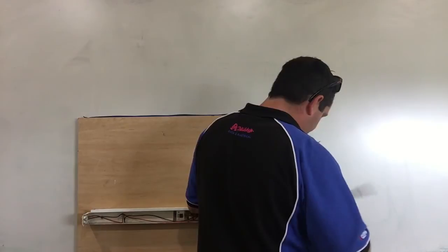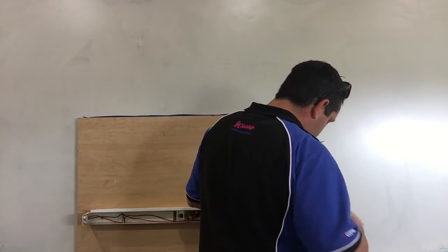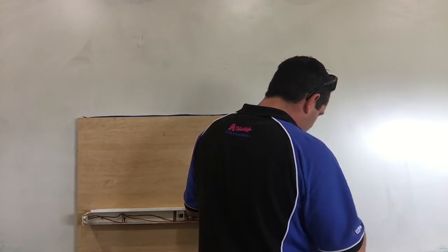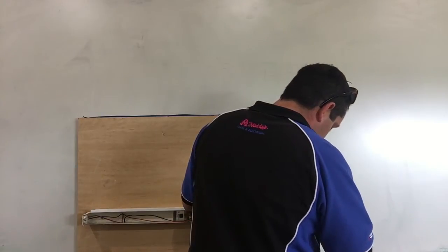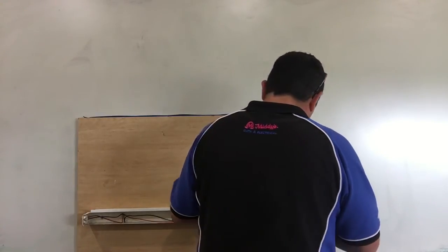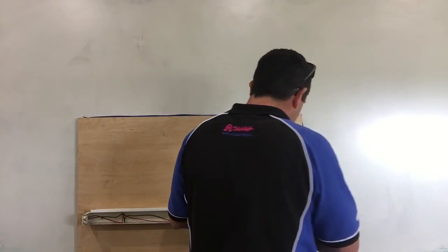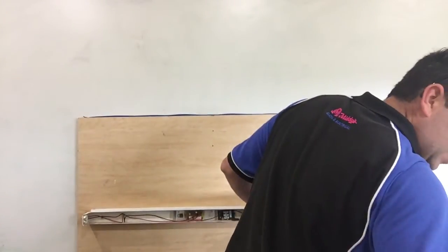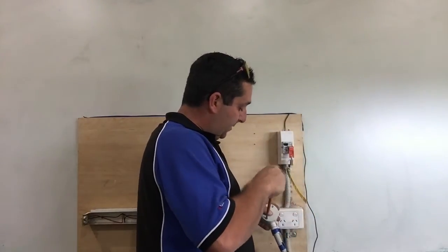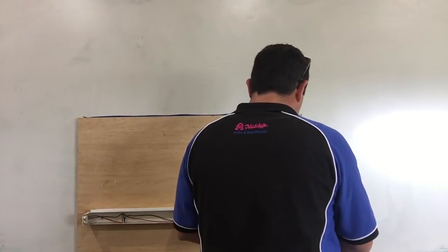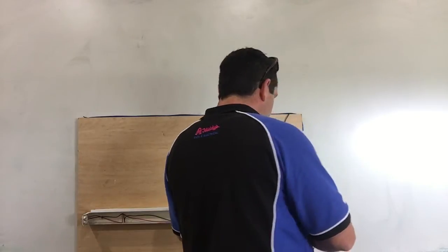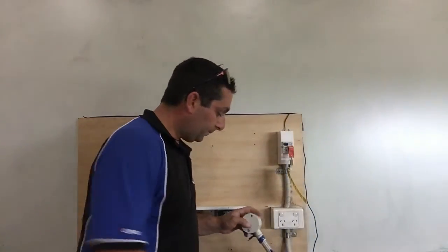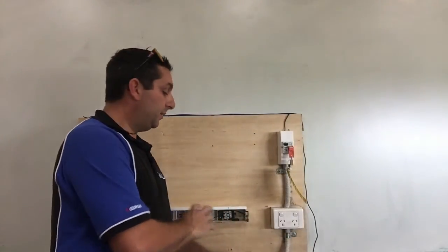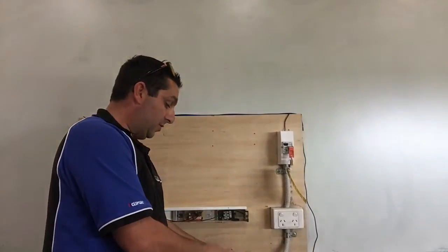So leave the neutral unwrapped. We can then re-unwrap the earth and test from neutral to earth, re-wrap, neutral to active, re-wrap, active to earth. And again, this is showing no voltage present, but we can't take that as being correct until we have tested our tester again to establish that it is still functioning correctly. So, cover back on. Active neutral, active earth, neutral earth. Our tester's working fine, so that's dead. So now we've established the appliance is fine and working. The cable that we need to connect into it is dead and not live.